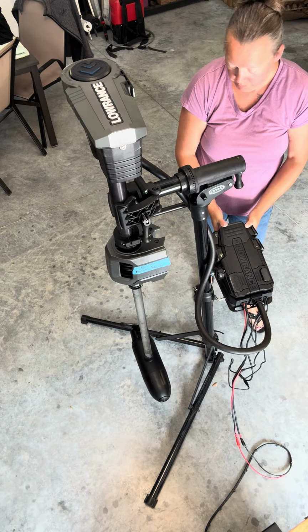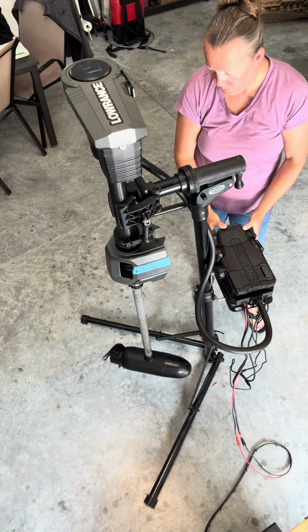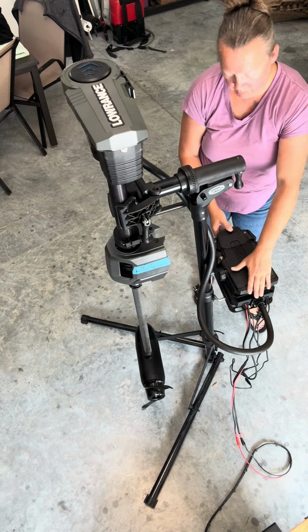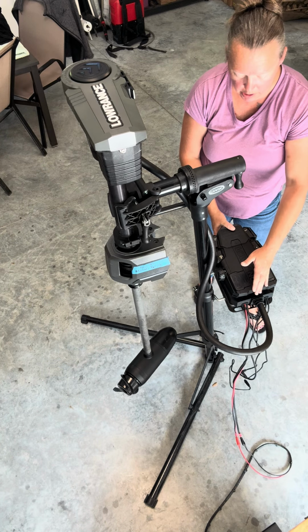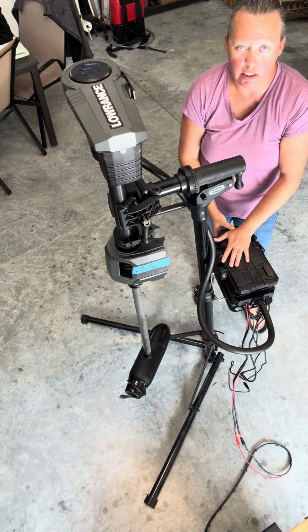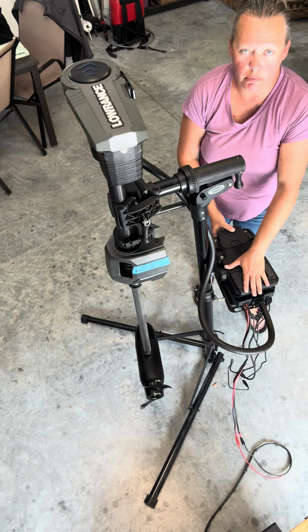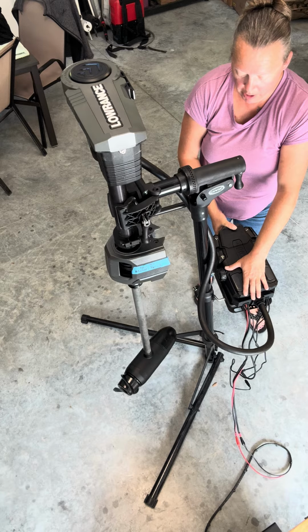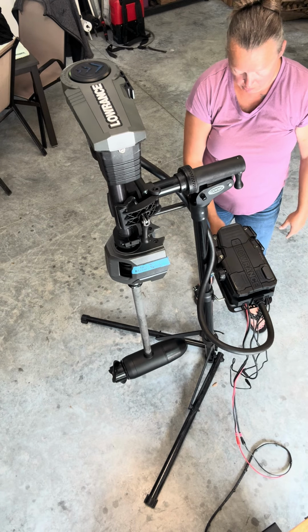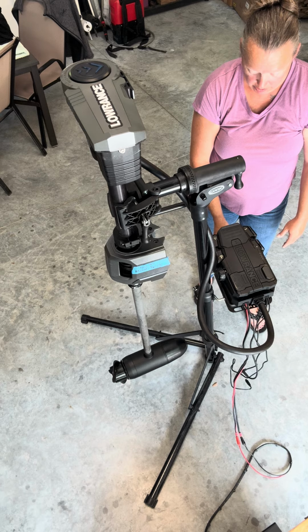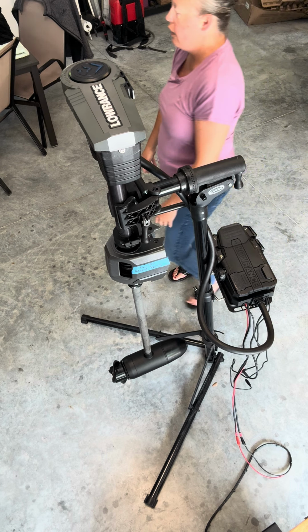Okay, so that means that the foot calibration needs to be done when it does that. It just means it's bottoming out, so the foot pedal isn't calibrated to the motor. So gotta do a foot calibration.